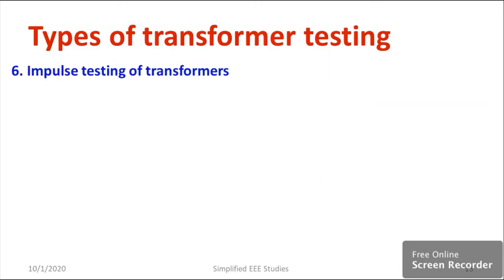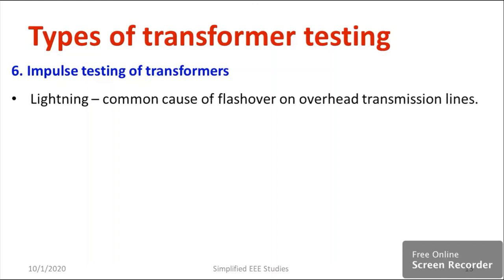Now I would like to discuss impulse testing, one of the most important tests for transformers. As you know, during lightning and thundering, a bulk amount of transient voltage occurs and directly affects the insulation of electrical equipment such as circuit breakers, isolators, and transformers. Transformers are especially severely affected by this kind of transient overvoltage, and most are located in substation yards, so it is very essential to conduct impulse testing.